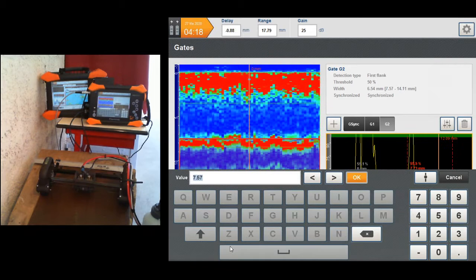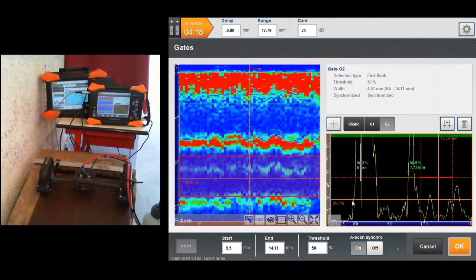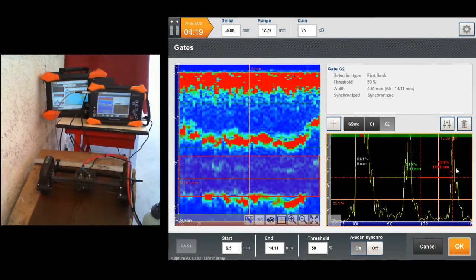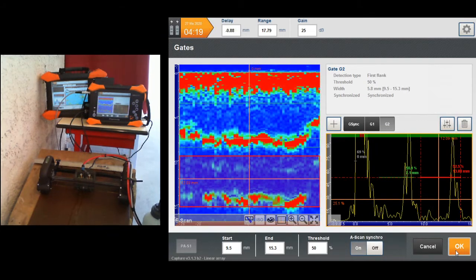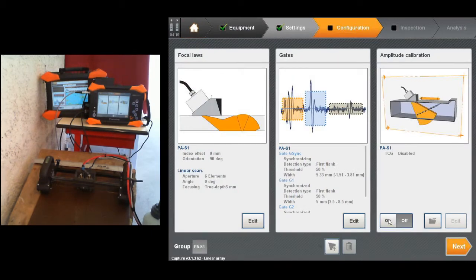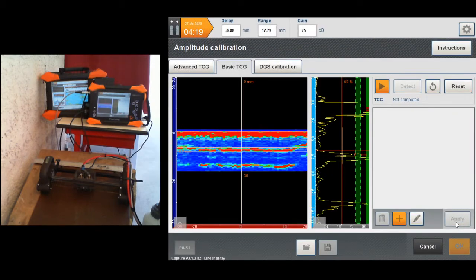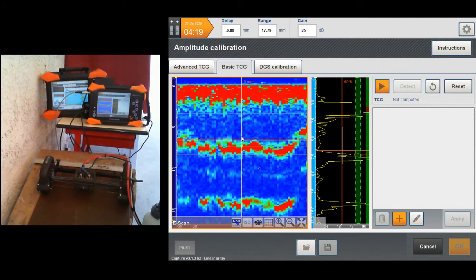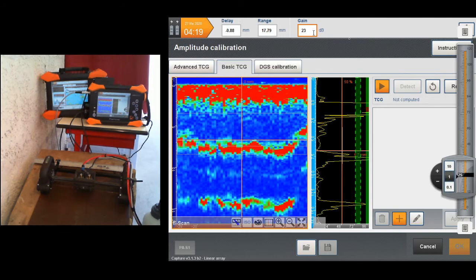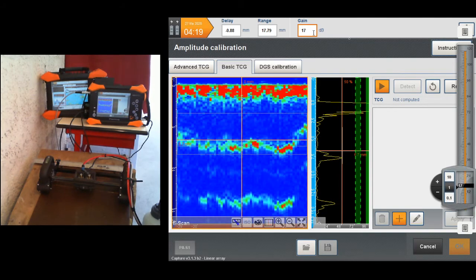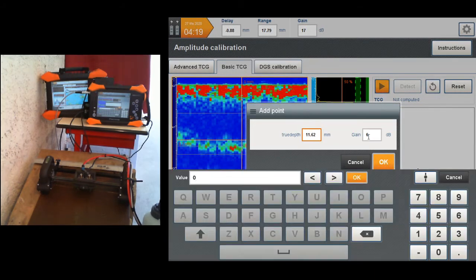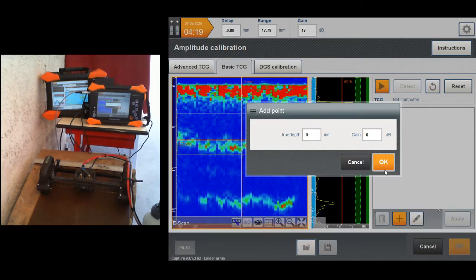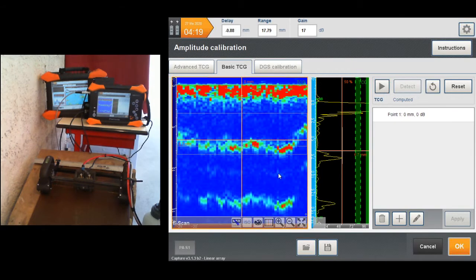Okay. I can start at 9.5. Okay, enlarge my gate a bit. Good. Then my gate setup is pretty good, and what I want now is to use calibration. What I like is to have quite a nice detection, even if it's always a matter of compromise between the gain and sensitivity. I don't want too much noise, but it's good to have echoes of high enough amplitude. And what I can set up here is a small TCG, so that I can have the same shape on the echoes, especially because I also use the first flank measurement.